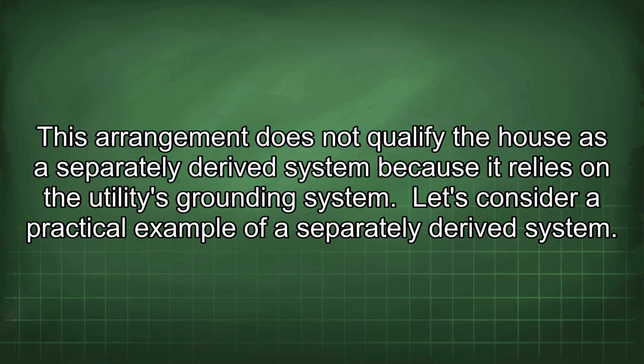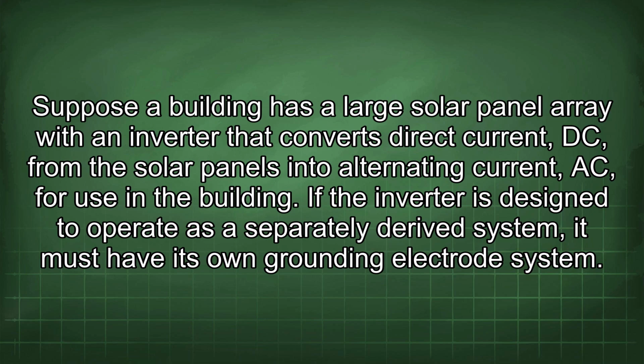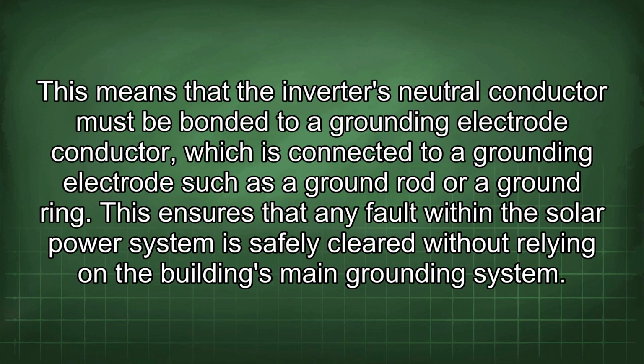Let's consider a practical example of a separately derived system. Suppose a building has a large solar panel array with an inverter that converts direct current, DC, from the solar panels into alternating current, AC, for use in the building. If the inverter is designed to operate as a separately derived system, it must have its own grounding electrode system. This means that the inverter's neutral conductor must be bonded to a grounding electrode conductor, which is connected to a grounding electrode such as a ground rod or a ground ring. This ensures that any fault within the solar power system is safely cleared without relying on a building's main grounding system.